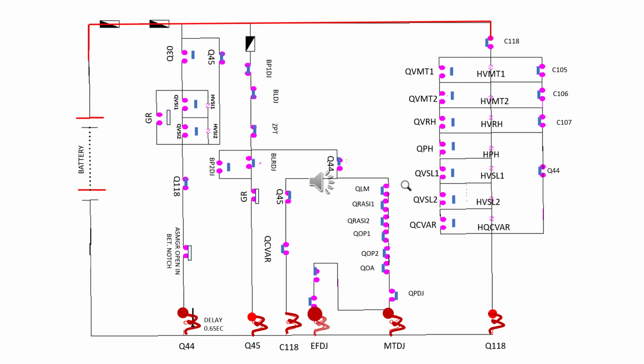So friends, we have seen first the Mtdj will energize, and after that the Efdj will energize, and these two coil energizations will enable closing the DJ. Mtdj will release the air in the DJ closed circuit left side chamber. Already I have shown in the previous slide, and it enables Efdj to press the DJ to close from the right side air pressure, which is coming due to energization of the Efdj.